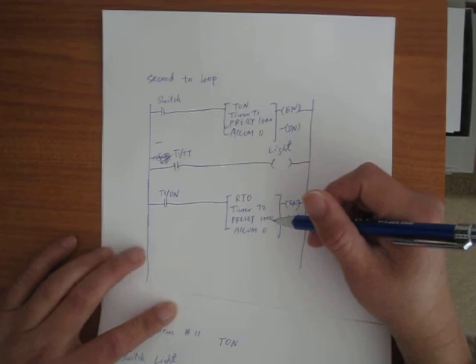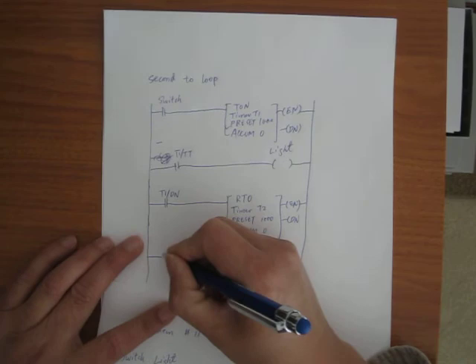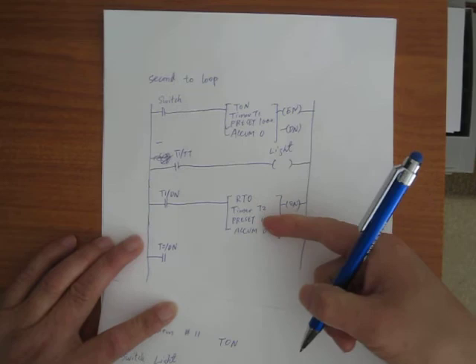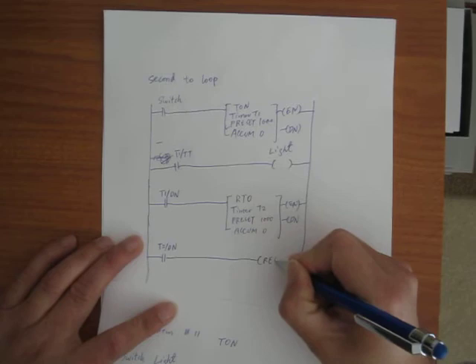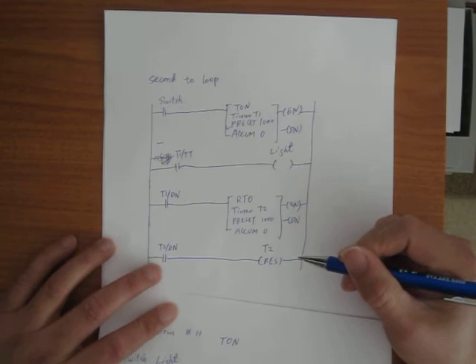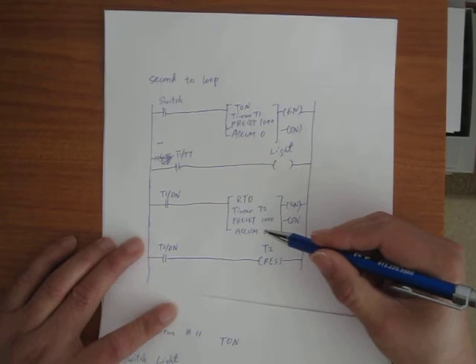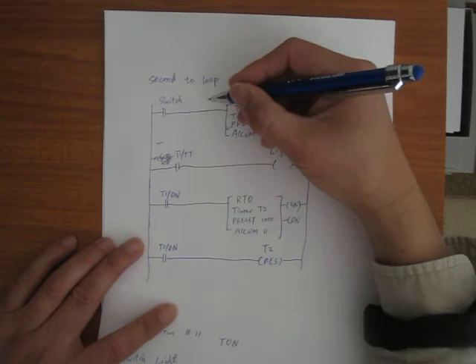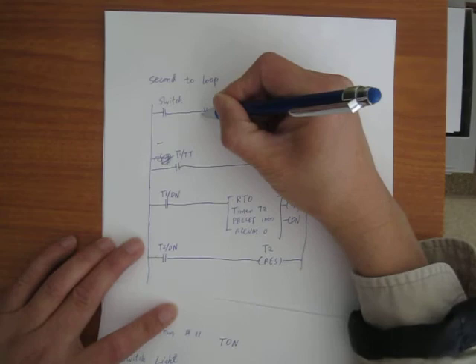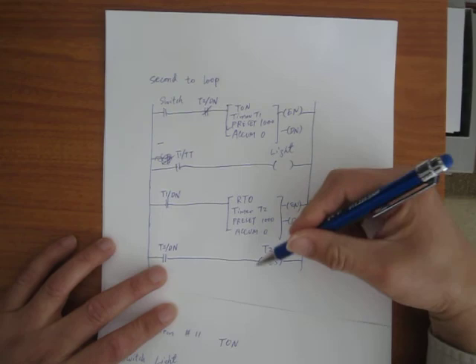After one second the RTO T2 DN becomes true. I'm going to use a reset here: when T2 DN becomes true, I'm going to reset T2. Resetting T2 resets the Accum back to 0. So I use a reset coil for T2 — when T2 DN is true, it resets T2.